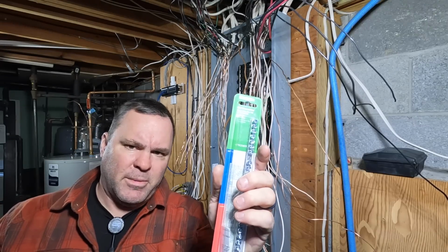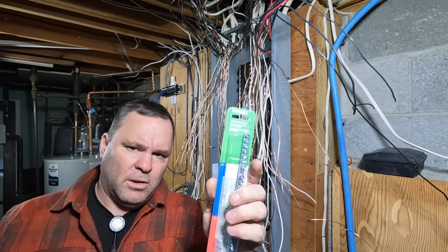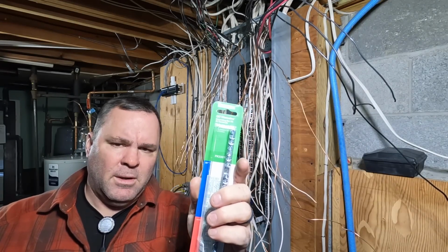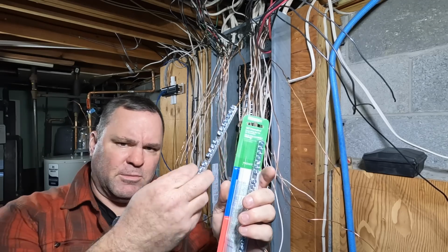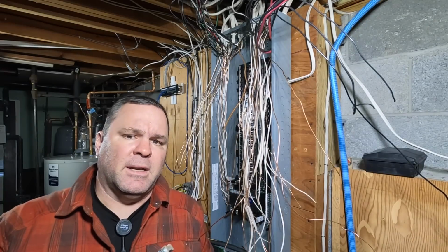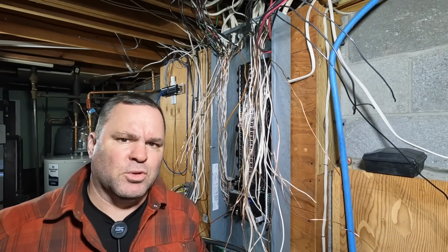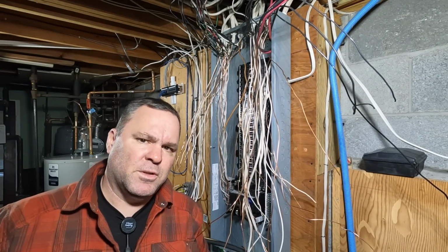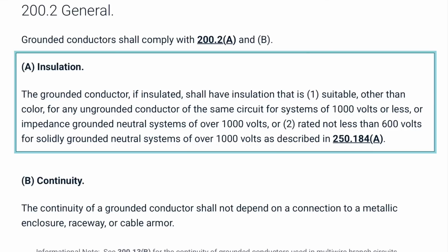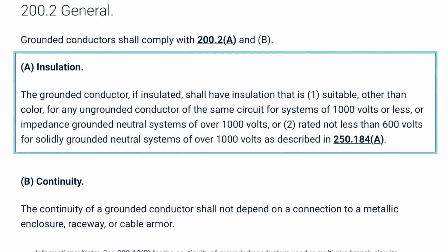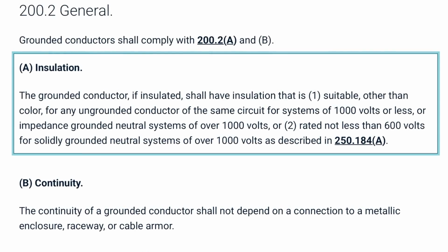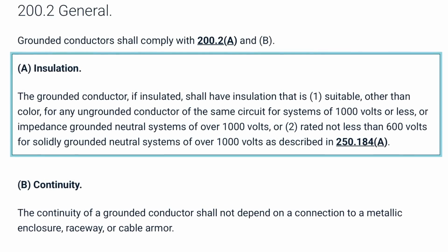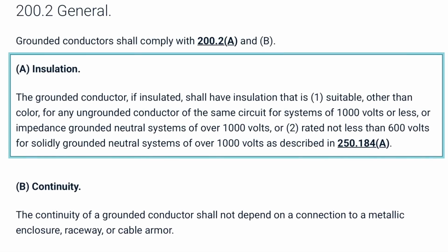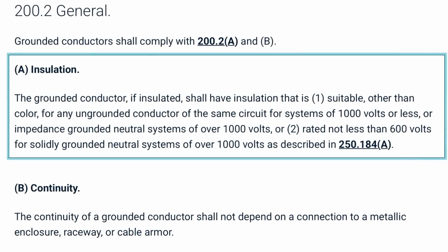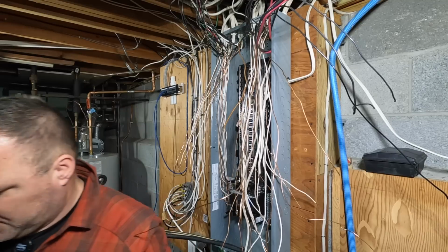And so what I'm going to do is I'm going to add this to the enclosure, and then I'm going to run a jumper from the original neutral bar to this bar when I install it, so that it's going to properly carry that neutral current back to the source for all the circuits that are connected to it. Section 200.2(B), the continuity of a grounded conductor shall not depend on the connection to a metallic enclosure, raceway, or cable armor. This is important because the neutral is a current carrying conductor.